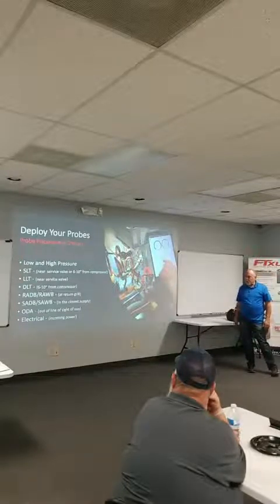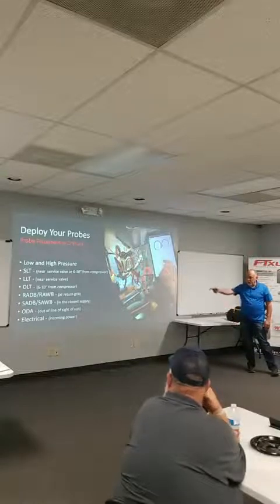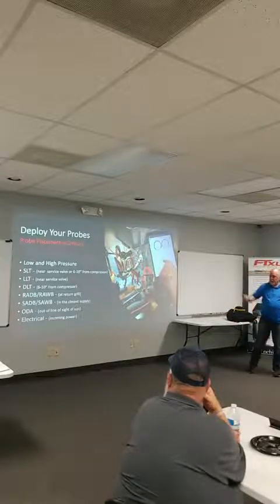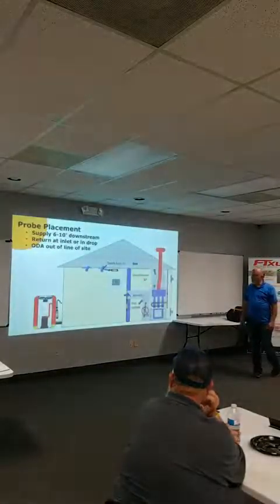Return air wet bulb and dry bulb at the return air grill. Supply air at the closest supply. Outdoor air out of line of the sun. And electrical, we always measure incoming power.